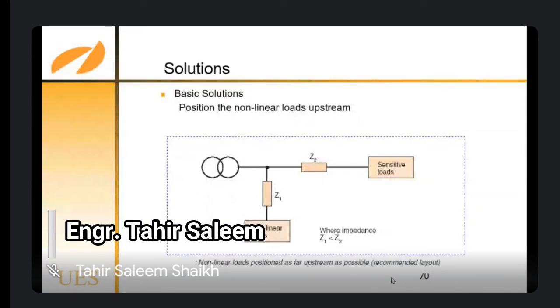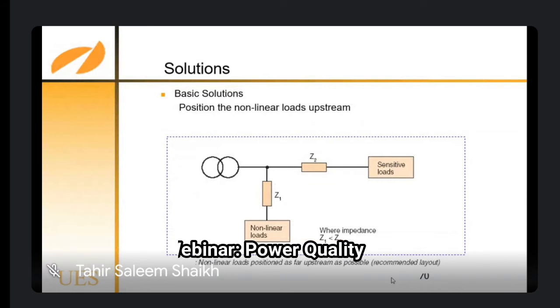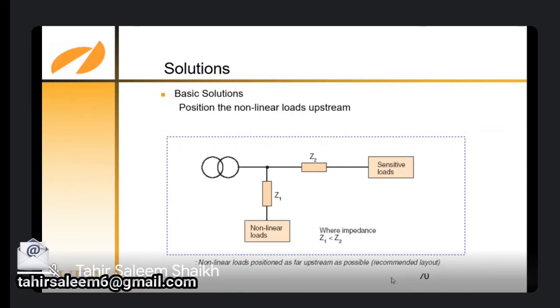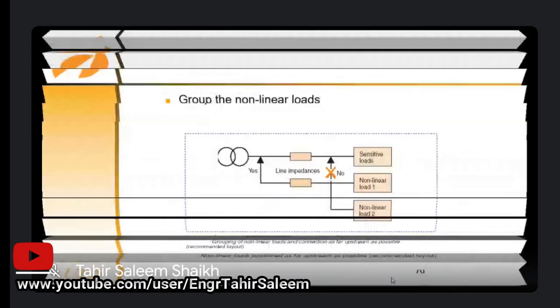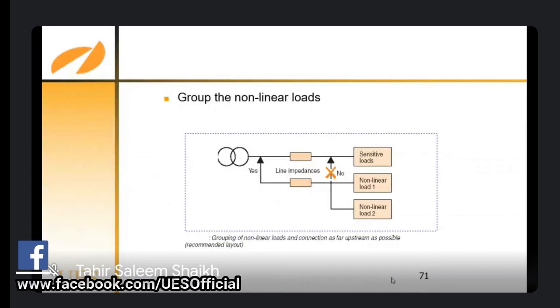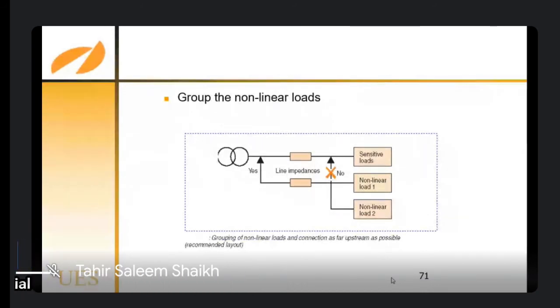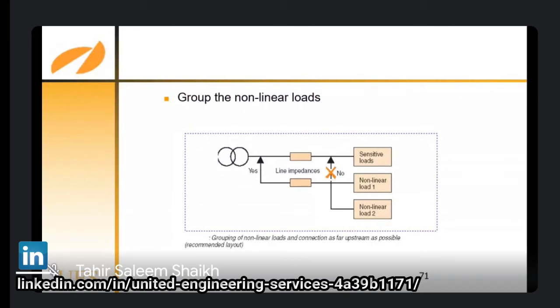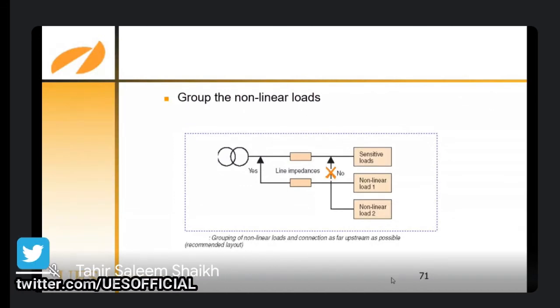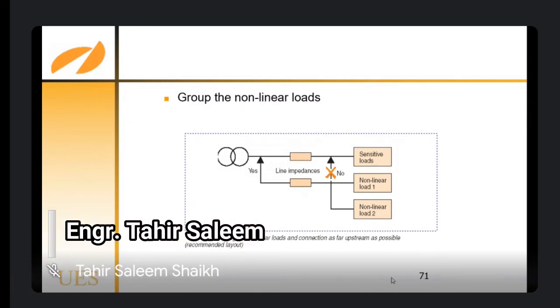This is one of the basic solutions: position the non-linear loads upstream. That way the impedance will be changed; the Z1 impedance will be less than Z2. The non-linear loads are near the power source, and the sensitive loads are remotely distant over here. Group the nonlinear loads. There should be a separate bus bar and a separate panel for the nonlinear loads, as you can see over here. The sensitive loads are separate, the nonlinear loads are separate, and nonlinear loads 1 and 2 can be taken from there. This is also a solution.